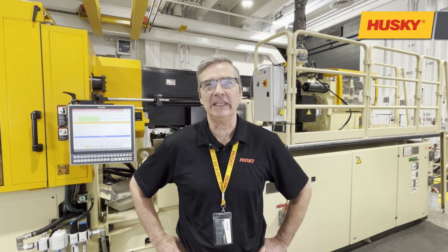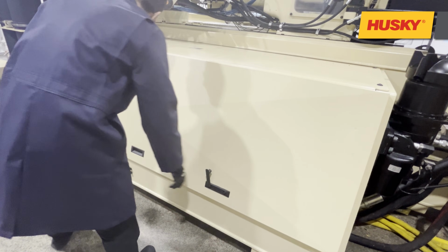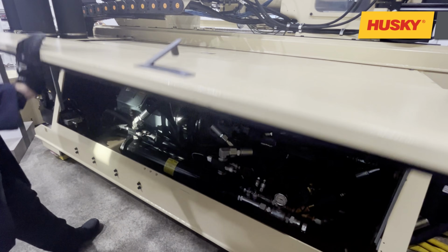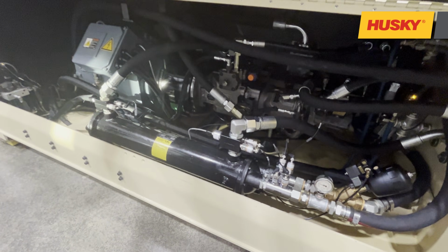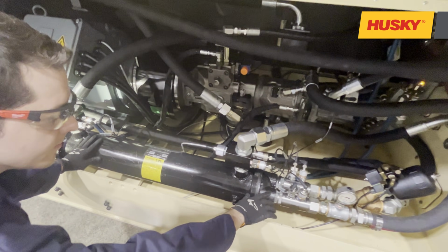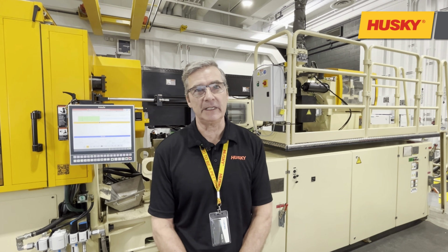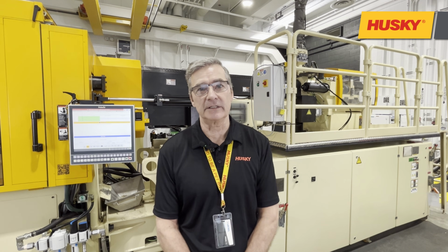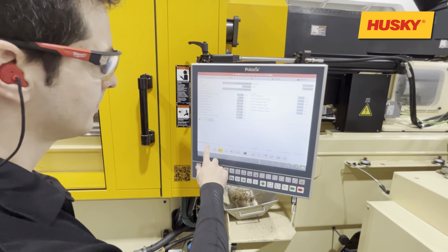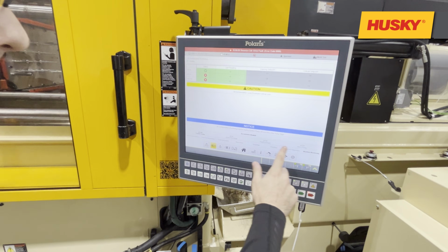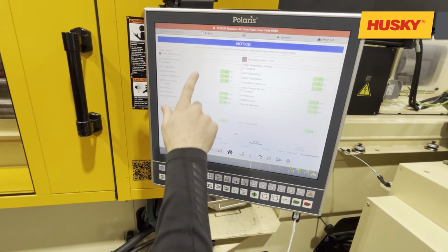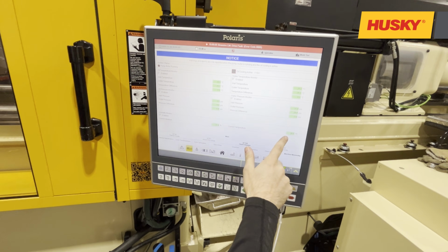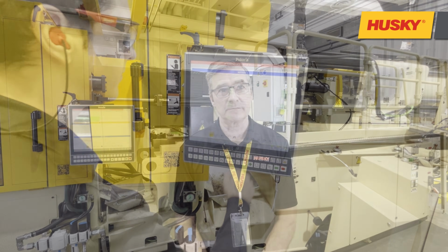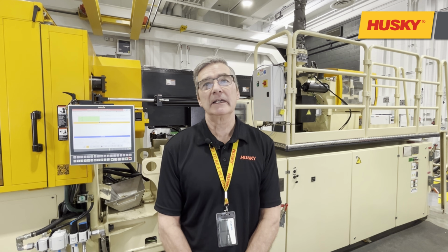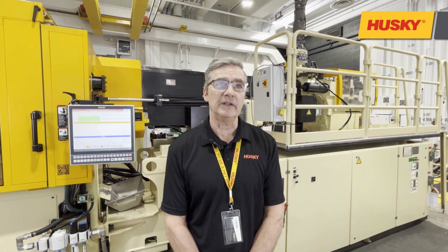Next, let's talk about heat exchanger performance monitoring. This package monitors both moisture in the oil and the performance of the heat exchanger. Moisture level measurements can identify water leakage from the heat exchanger, as well as dissolved water from ambient humidity, providing the customer with the earliest opportunity to address the issue. We also monitor pressures and temperatures to track heat exchanger condition. In addition, we monitor supply water for early diagnosis of tower water issues long before high oil temperature alarm occurs. Changes in the water pressure differential can help us diagnose fouling of the water tubes, while on the oil side can identify issues with the filter pump.